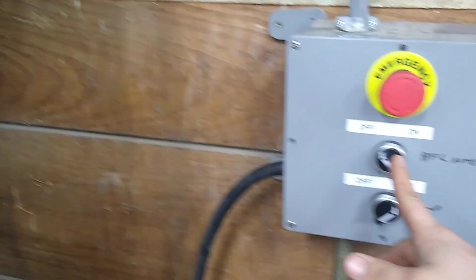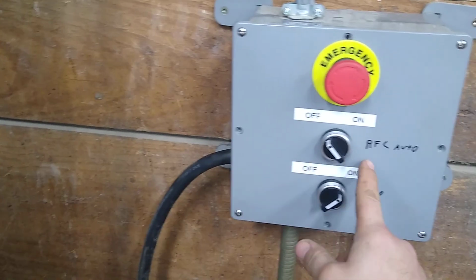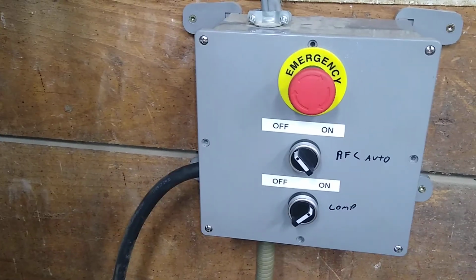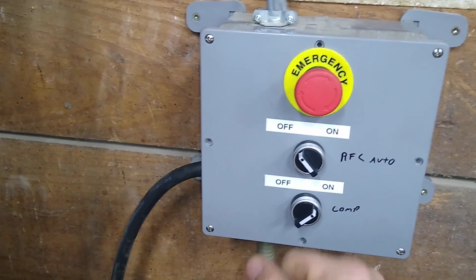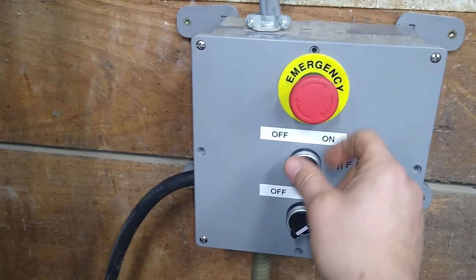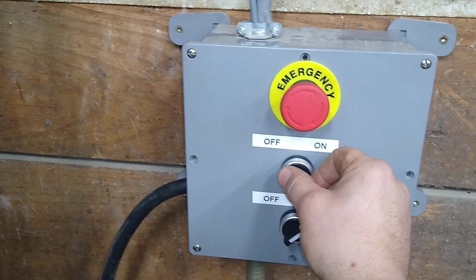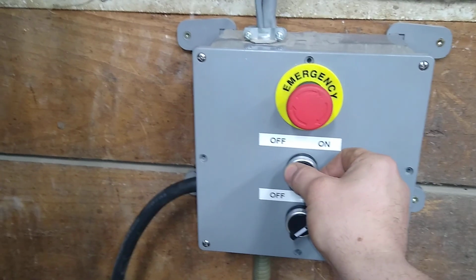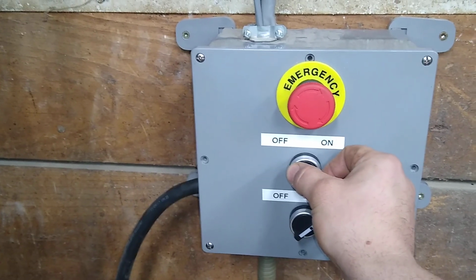So now I'll just go ahead and turn on the rotary phase converter auto, because right now technically the compressor is enabled. It's already calling, but it's interrupted by this. So what's going to happen is the rotary phase converter is going to come on, and a half a second later, the compressor is going to try to turn on.